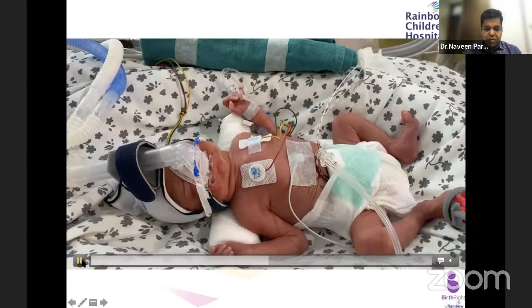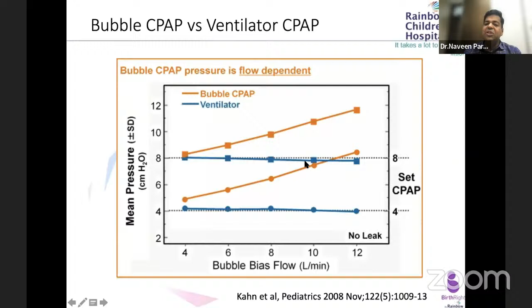So bubble CPAP pressure is flow dependent, as I was explaining to you. See here, the mean pressure is 4, right? And as you increase the flow, look at the pressure. So at 6 liters, the pressure is different, although the set pressure is the same. The orange line is the bubble CPAP. As you increase the flow, the pressure increases. And in the ventilator driven CPAP, because it is not flow dependent, the pressure remains constant.